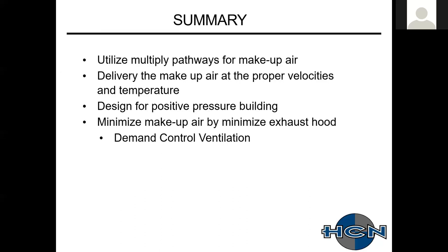Cross drafts are usually a major concern from a lot of stuff. If you have island hoods, typically your exhaust rates are a little bit heavier on those. If you're utilizing makeup air for hoods where it's integrated, you can get plenums that go all the way around the hood. So that way we try to minimize that PSP size as much as we can because we want to minimize that diffusion. And then demand control ventilation systems.